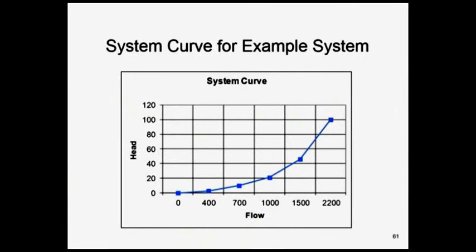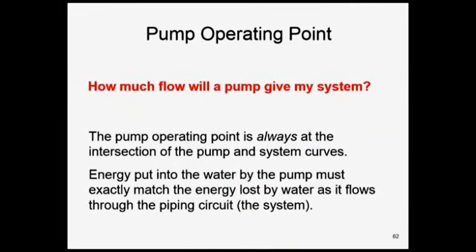And that's what's important to you to understand if we're going to do balance, and we're going to relate the pump to balance and start bringing this all together to see how we can save some money. So the next thing we're going to do is take this system curve and put it on a pump curve. How much flow will a pump give my system? You bought this brand new pump at 2,200 GPM at 100 feet of head. How much flow will it really give my system?